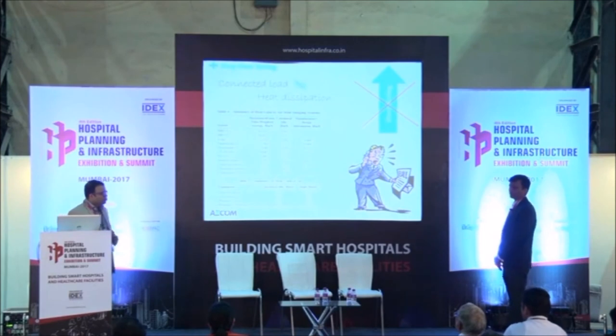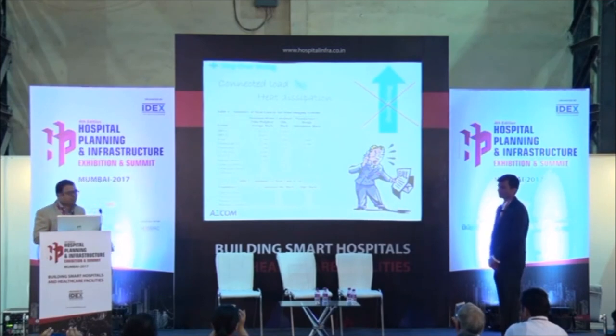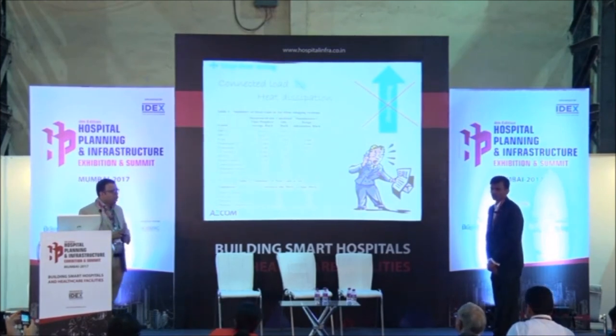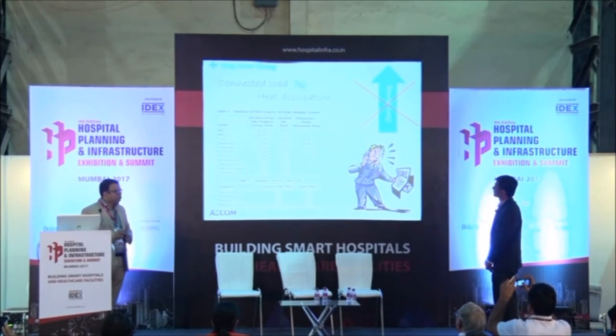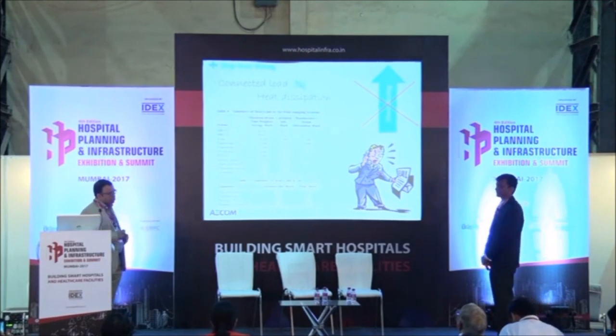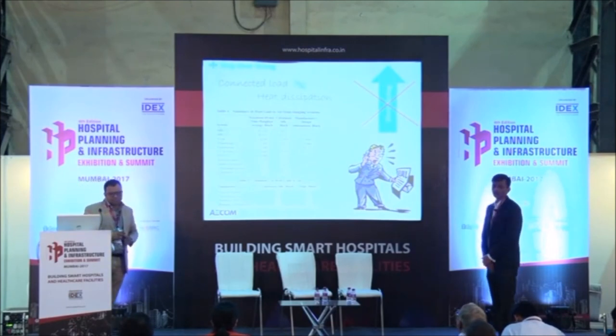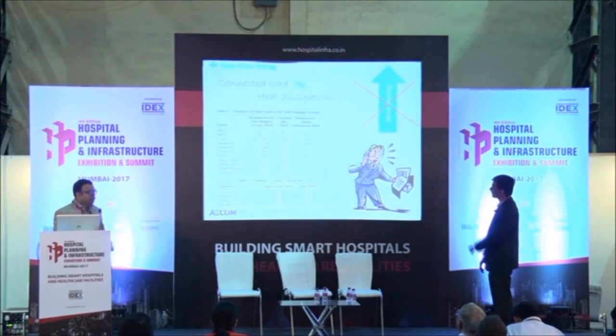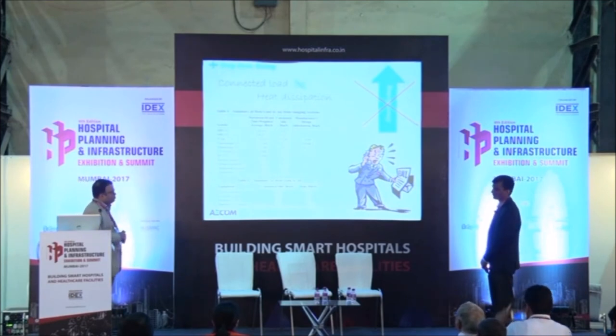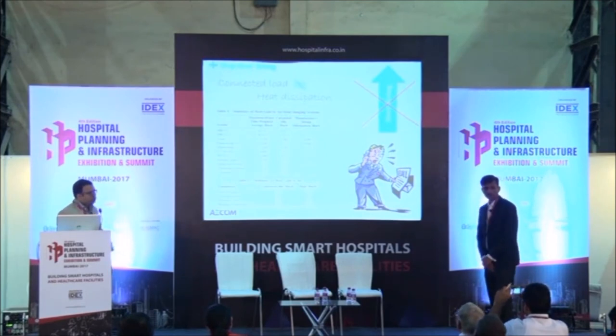This is a very interesting slide for design engineers. When doing initial calculations to estimate the cooling load of a particular area, heat generation is the heat input for an air conditioning engineer. The usual way is to take connected load as heat dissipation and get away with it. It is interesting to know that connected load is never equal to heat dissipation. For example, an MRI machine's connected load can be 100 to 200 kilowatts, but the heat generation is only to the tune of 20 kilowatts. So it is very important not to over-size the system. There are two guidelines available in ASHRAE for taking equipment load as input that can help avoid over-sizing.